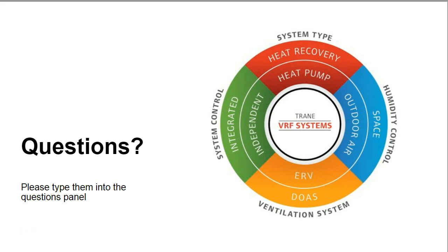Another question is, are there any problems with noise from the control box and heat recovery systems? Yeah, so an appropriately sized and designed VRF system should have minimal noise generated by the heat recovery unit. Also, I do not recommend putting these boxes in occupied spaces in which low-level noise is required. So my first point of advice when placing the branch controllers, and that goes for all different manufacturers, is to find some sort of service closet, either a mechanical room or a hallway, where, like I said, the low noise level is not going to be a factor.